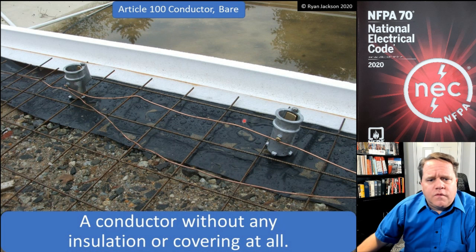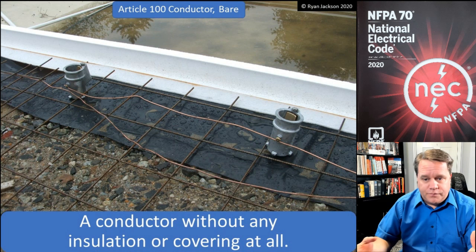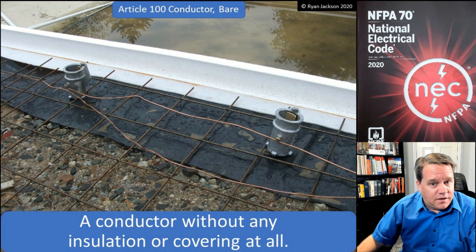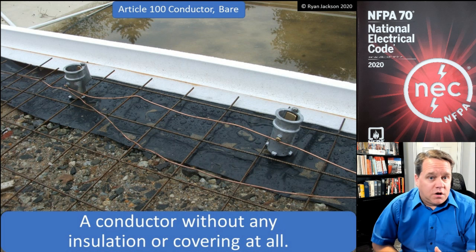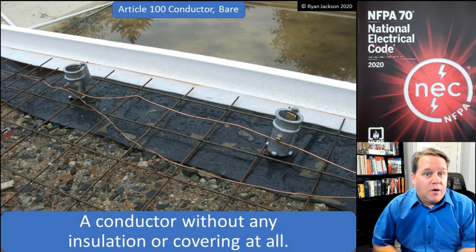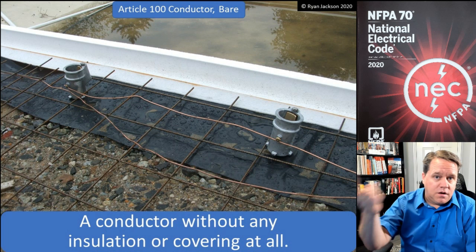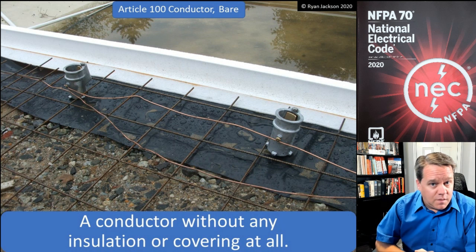Here we've got some bare 8 gauge copper used for bonding ladder cups around a swimming pool as well as the mesh for the deck — that's a bare conductor. Another example would be a grounding electrode conductor going to a ground rod, or a bare conductor overhead used as the neutral on the line side of the service equipment.